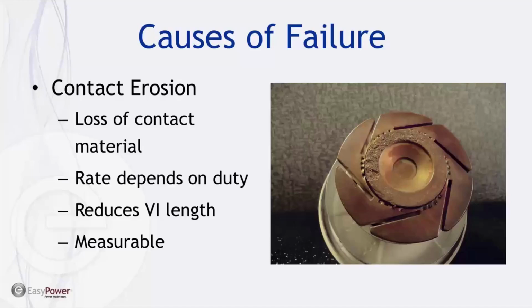So one thing about this contact erosion is it's a measurable thing. All vacuum circuit breaker manufacturers will specify some way of determining the amount of contact erosion. In many cases, it's a measurement where they give you some starting measurement and then an end of life measurement, where if it reaches that point, the vacuum interrupter needs to be replaced. Some manufacturers have some type of visual indication, whether it be on the wipe spring itself or sometimes an actual physical dot or mark put on the moving shaft of the vacuum interrupter, where when that dot or mark recedes inside of the vacuum interrupter when it's in the closed position, then that vacuum interrupter needs to be replaced. But again, this is something that's measurable and can be tracked over time and replaced when it reaches that point.